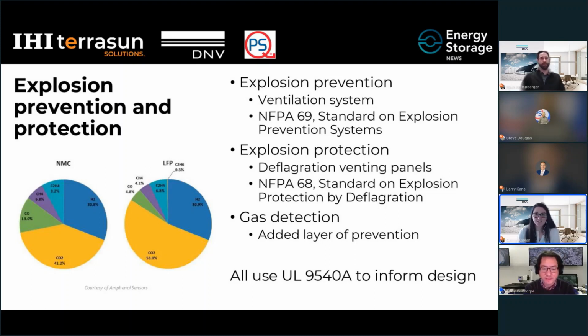Sure, great question. UL9540A is designed to inform on the extent of thermal runaway that a system can undergo, so this is directly linked to how safe the battery is, but the tests also inform on what safety features are additionally needed, as Mark discussed earlier. So just because a BESS has gone through testing doesn't necessarily guarantee that it's safe. DNV definitely recommends adhering to the latest standards and regulations, such as NFPA 855 and IFC 2021, to increase the safety of the system.